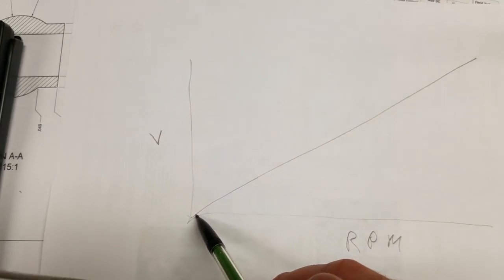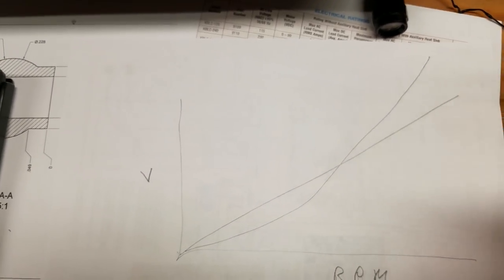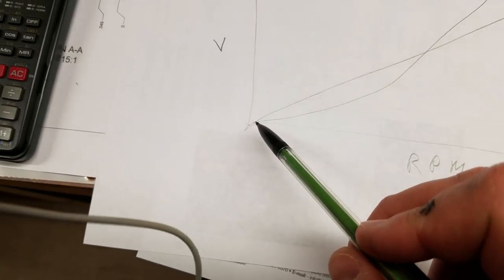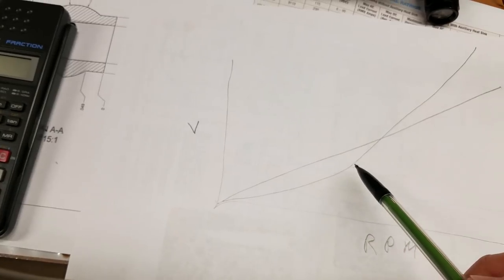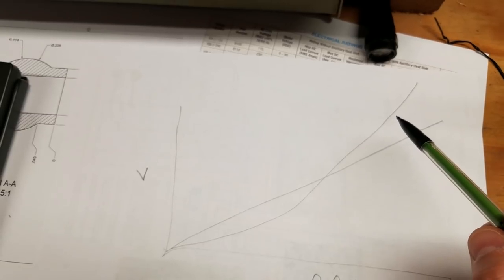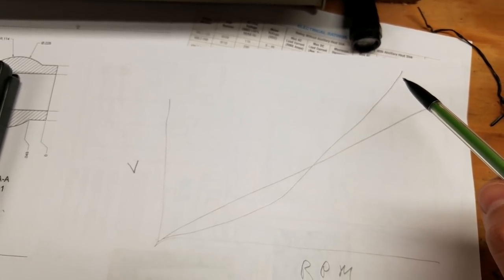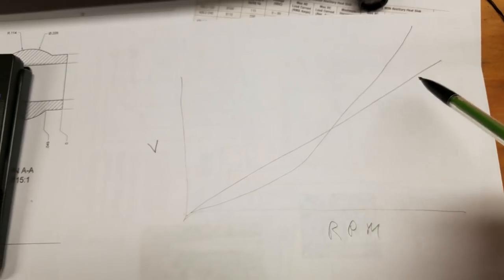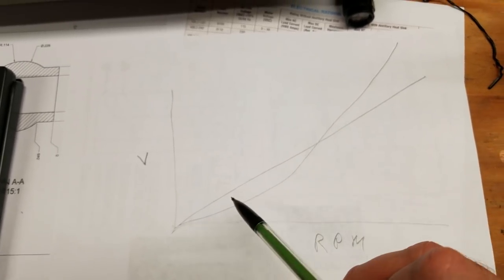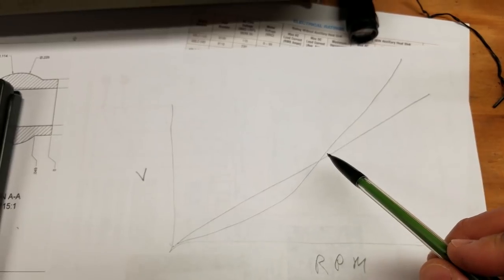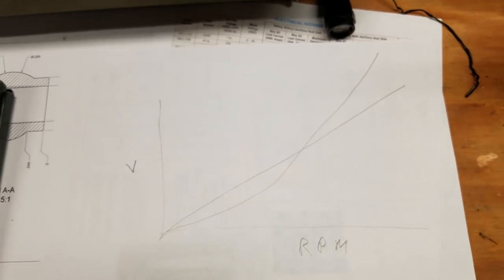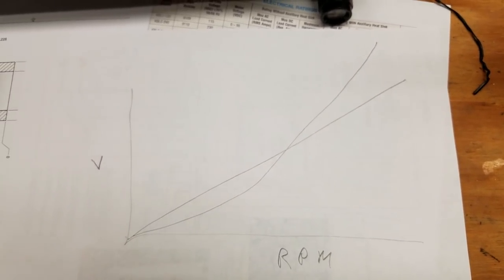So what's happening? As you're at your slower RPMs, you're a little less than what you command, and at your higher RPMs, you're going to be a little more than what you command. I may not have drawn that exactly perfectly, but you get the idea. So VFD, very linear. It's going to be very linear in the way it reacts to the control signal. DC spindle drives, not linear. They're going to have sort of an S shaped response curve. And I have a feeling I may look at this video after I make it and think that I may have drawn this curve, maybe not exactly 100% correct, but you get the idea.